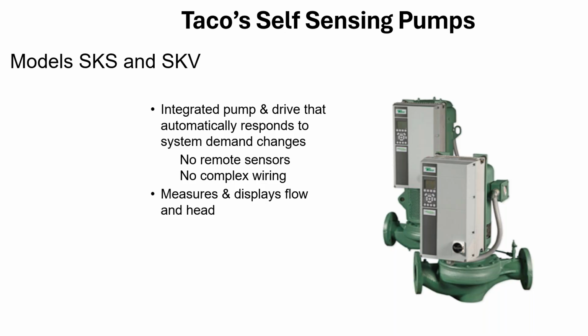Another nice thing, it's very difficult to see. Where the heck's my mouse? There it is. Right there's a screen. It actually displays flow and head right there, as long as you're in the right screen display. So it measures and displays flow and head for the system. And trust me, I've been in enough mechanical rooms trying to find it, let alone if it's working correctly, the flow meter, or if it's pegged or whatever. So something like that. And the drive is capable, because of its internal smarts and programming and all of the testing that we do at our factory, to measure actual system resistance.